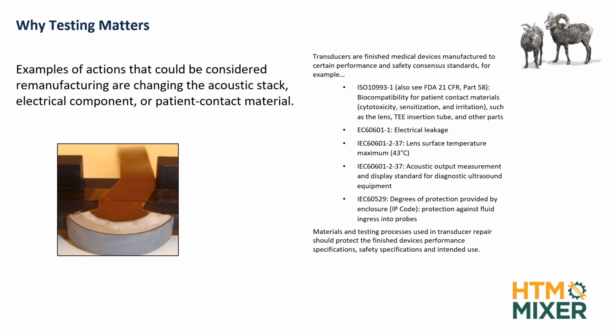So here's just a few of them, and these are basically focused on the ultrasound probe. There's a couple more that are added from the system software, and hopefully nobody's out there trying to change the code on the software as a third-party repair function. So here are the five bullet points that really take a look at each one of those things. So you read those and you go, okay, I have to make sure that the electrical leakage is right. You have to look at that for ultrasound probes, under 50 microamps of electrical leakage in use, etc. If you're using improper materials or you're not performing the replacement of a lens correctly on a transducer, you can create paths for fluid ingress and also electrical shock.